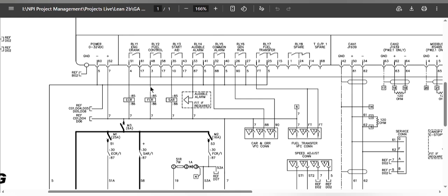Okay? Check with the multimeter and start to crank, and check the output at this pin 48, as you can see, and check that you are getting the system voltage between positive and negative. That means the controller is working and sending a signal to the fuel control relay. After that, check that the fuel relay is energizing, and then check the relay load contacts, normally open and normally closed. You should check the relay normally closed contact during the relay energizing.